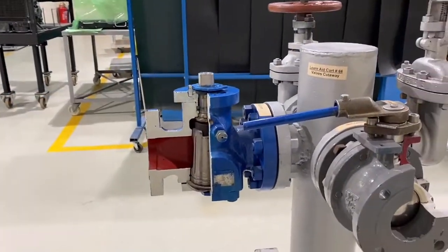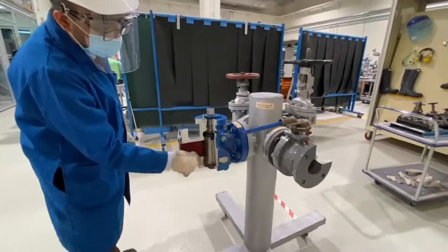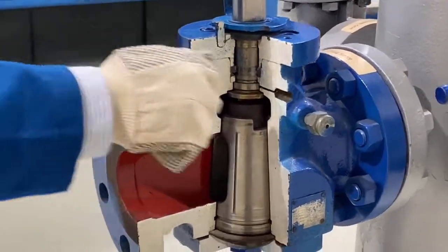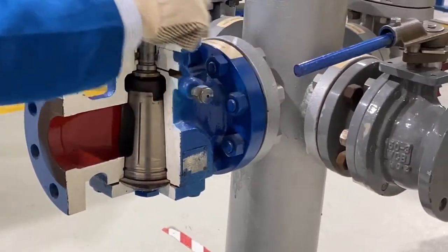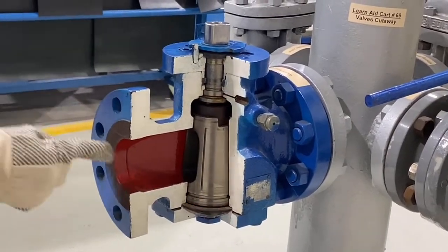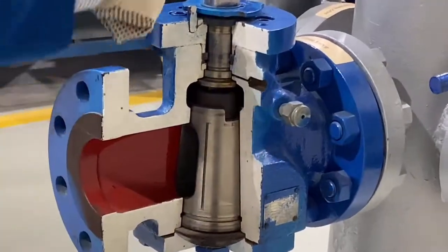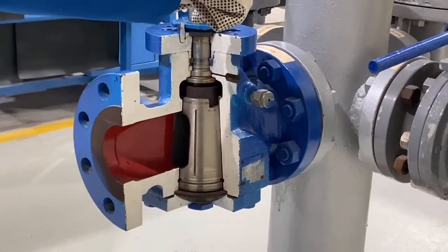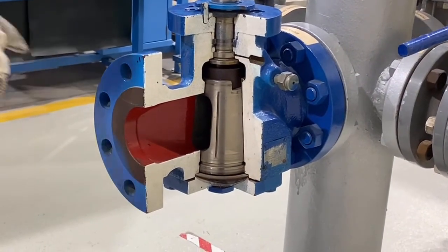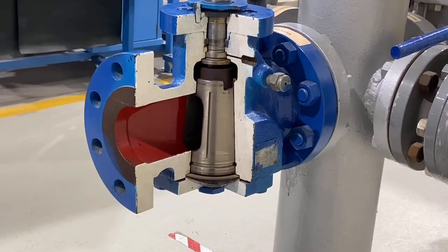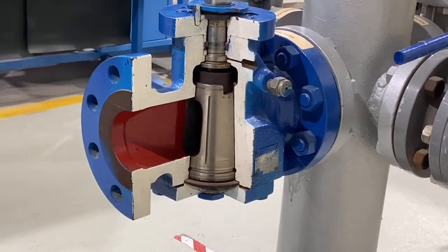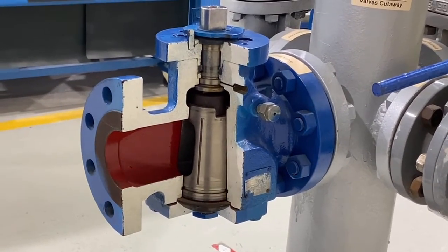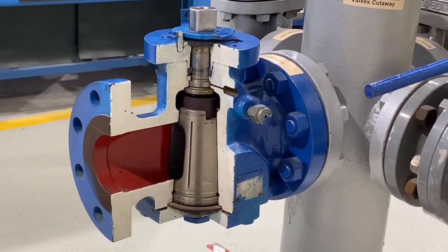This is the plug valve. Here the main isolating element is a plug, but normally there should be a handle, but the handle is not over here now. Here also, like a ball valve, if the handle is in line with the line of flow, it is open position, and if it is perpendicular, it is closed position. This is also a quick opening valve because a quarter turn or 90-degree turn will make it fully open, and it can make it fully closed if you turn backwards 90 degrees. A quarter turn will make it fully open or fully closed. So it is a quick opening valve.